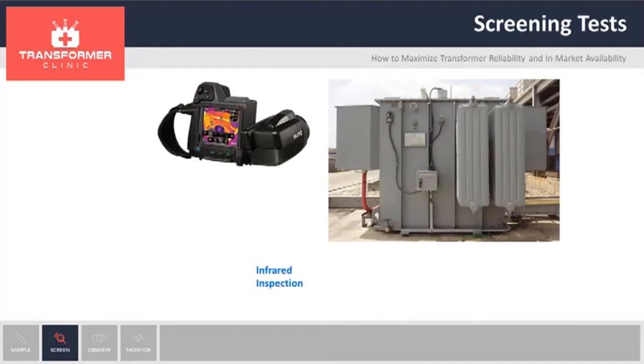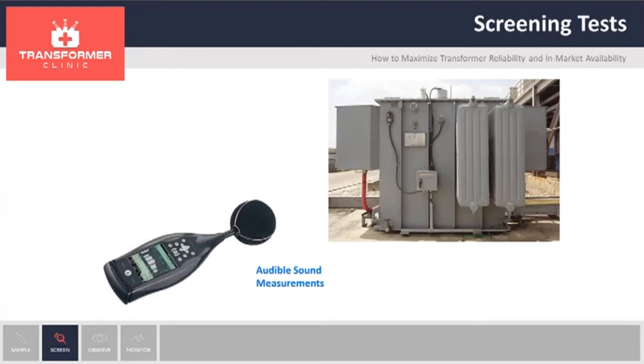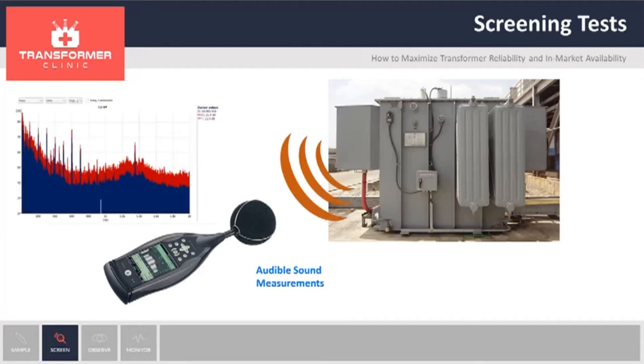We complement that with infrared inspection. Infrared can be used for looking for problems with the cooling system. We can look at low oil levels, see sludge on the bottom of the transformer, or see overheating of tap-changer compartments, which might indicate contact damage or contact degradation. An optional test will be an audible sound measurement — if utilities have complaints that the transformer is too noisy at night, we can characterize what frequency the noise is coming from and under what conditions, which can help remediate the problem.